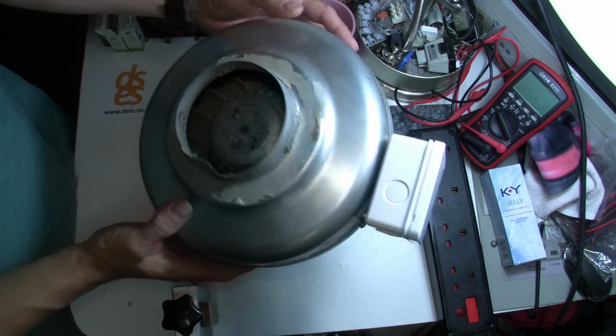But has it killed the fan by pulling the neutral? Let's take a look. There's nothing on fan line and neutral, nothing on fan line with respect to supply neutral, and nothing on fan neutral. So the Manrose is behaving according to expectations by cutting the supply to the fan. Marvellous! I wonder if the gizzards are the same in these Manrose and Swift Air affairs.